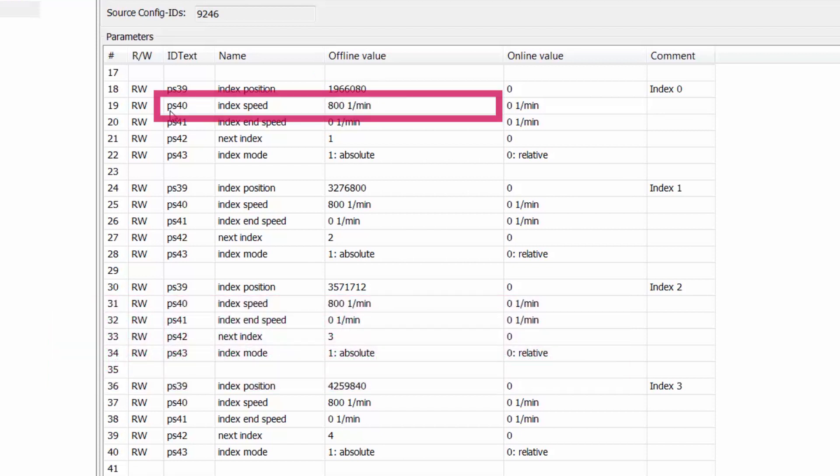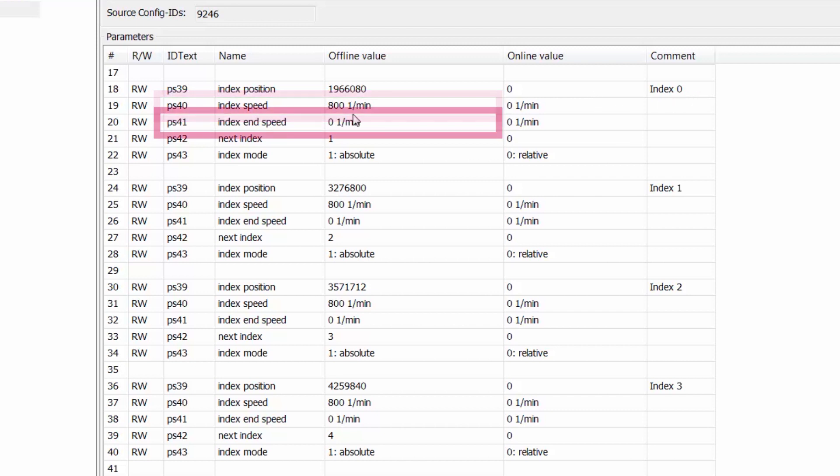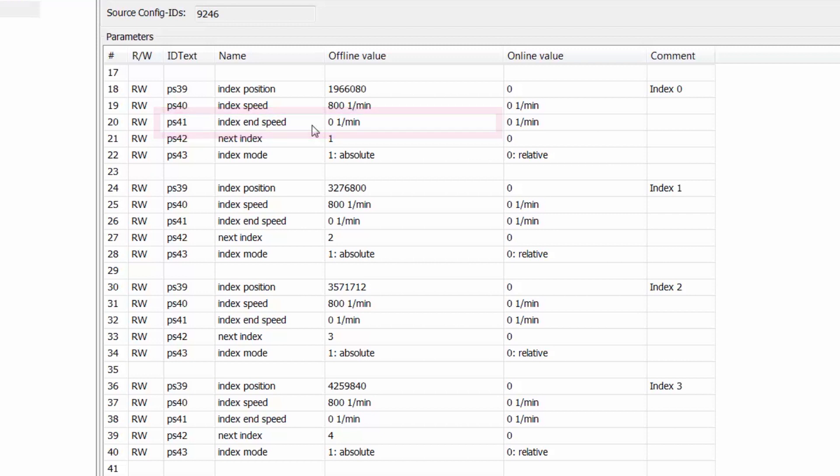The second parameter PS40 index speed represents the speed at which this program position is obtained from the drive's previous position. PS41 index end speed represents the speed at which the drive will obtain at the end of the positioning move. We always want this set to zero so that when the drive reaches this position the drive will reach a zero speed.